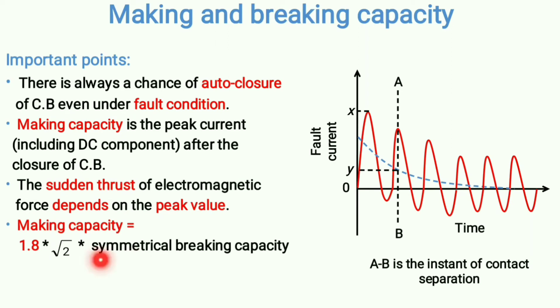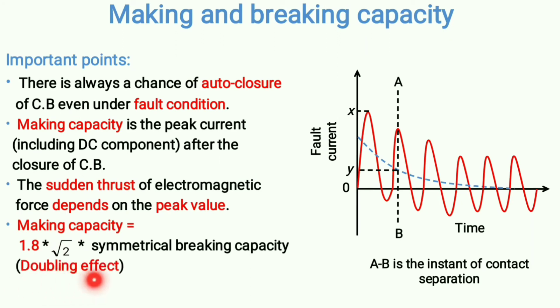The formula for making capacity: first, multiply the symmetrical breaking capacity by √2. Symmetrical breaking capacity is X/√2, so multiplying by √2 gives X — the maximum value of the symmetrical fault current. Then multiply X by 1.8 to account for the DC component. The reason for 1.8 relates to the doubling effect — all these topics are interrelated and vast.